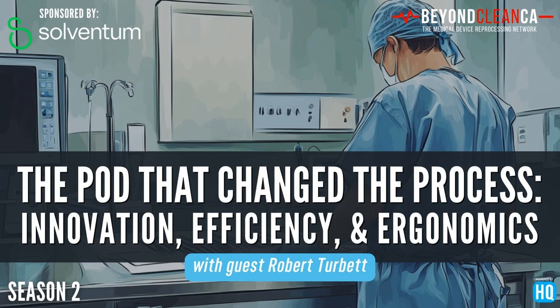In the U.S., the pod is a class 2 medical device, which means we had to get an FDA clearance to use the device. We had to go through the 510K process, and we received our first 510K, I think back in 2017. Part of that process is that we have to show sterilization efficacy. There are standard tests that we run in an independent lab to prove that this works. The FDA also says you need to claim what size lumens and how long they are. Literally a month or two ago, we received our latest 510K, where we took the lumens down to 1 millimeter in diameter by 850 millimeters long. And then we also did a 0.7 millimeter lumen by 500 millimeters long.